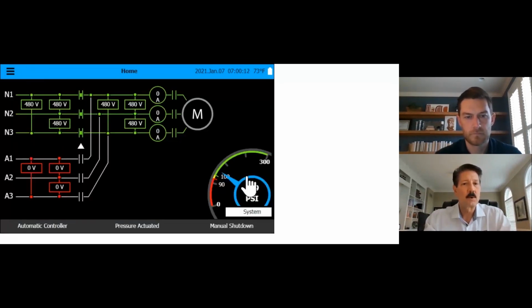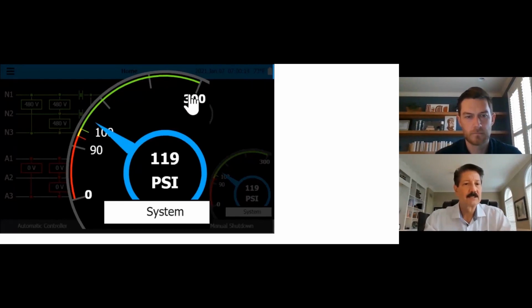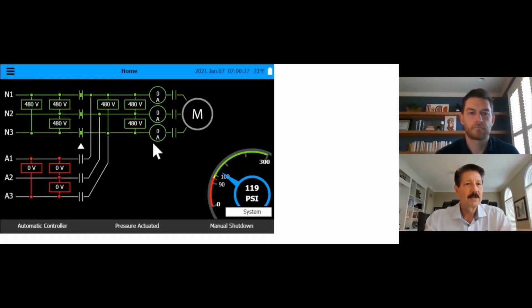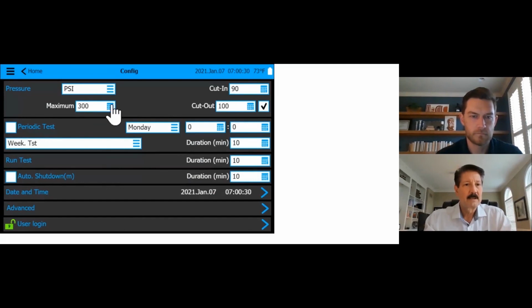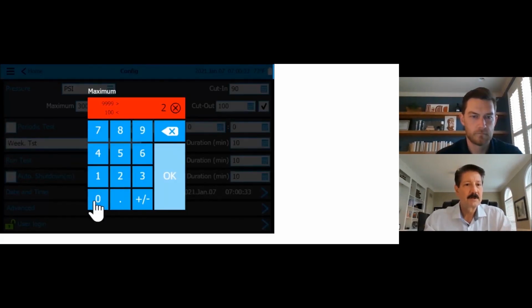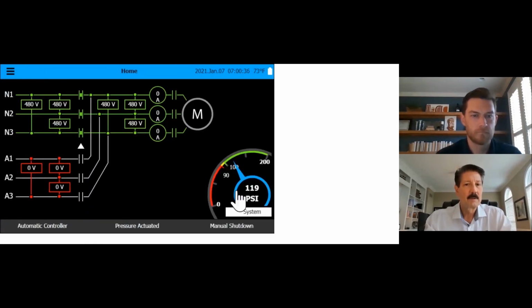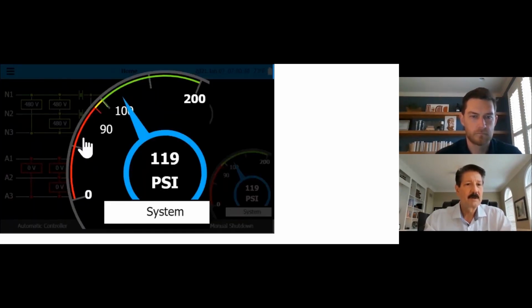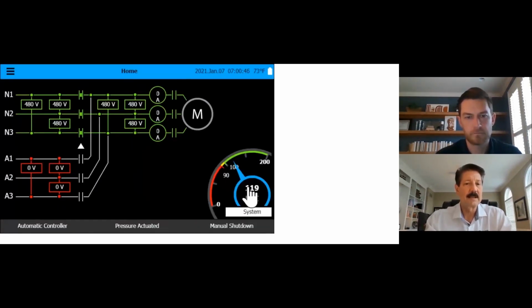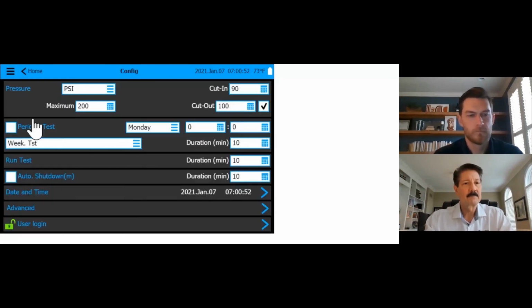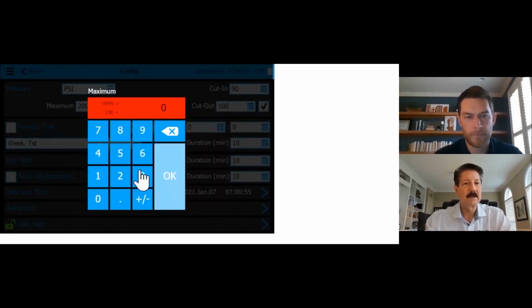For example, let me put you back at home here. This scale is from 0 to 300 PSI. But I have quite a lower pressure here. If I'm not going to exceed over 100 PSI or 119, I might want to squeeze that down to 200 PSI, and I'll show you what it does to the system. If I were to just change this to 200 and go back to home, it spreads this open a little bit wider, 0 to 200 PSI. It's a lot easier to visually see it when you look at it, whether it's in the enlarged version or on the screen itself. Just a little thing I wanted to point out because I do get questions on that.